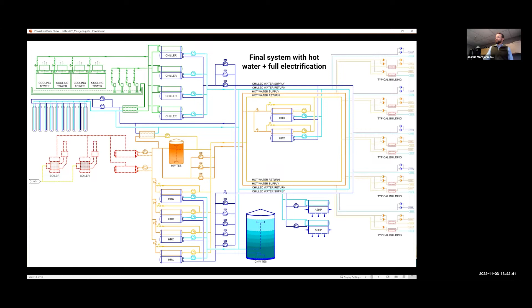As far as what happened over the last 2 years, the pipe went in the ground. This is one difference from what Stanford did - we learned a lot from them and tried to follow in their footsteps, but one thing we did differently is we went with a high temperature HDPE pipe. It's a plastic pipe that can go up to 180 degrees operating temp, which made installation a little easier using fusion welding, and that pipe is installed in these trenches.